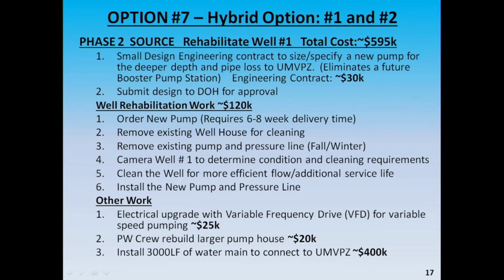I'm thinking my public works guys will remove that existing well house, get it out of the way. It would include the costs of pulling that old pump out and the pressure line, camering the existing well, determining the cleaning requirements, and then basically installing a new pump and new pressure line. And then the other things that would need to happen in conjunction with this is we'd like to put in a VFD, variable frequency drive, so that we can operate that pump at different speeds, which will allow us to regulate how much water we pull out of there.